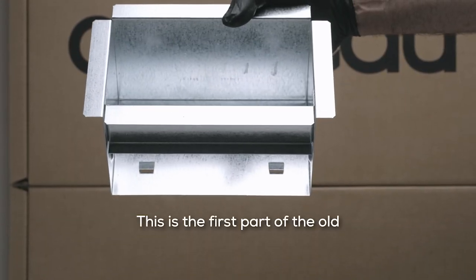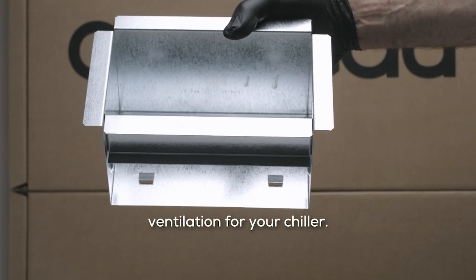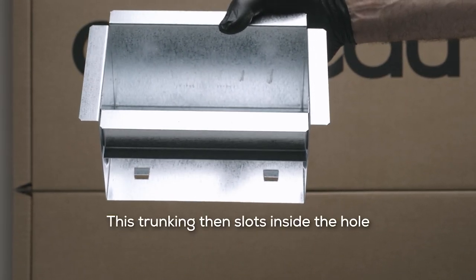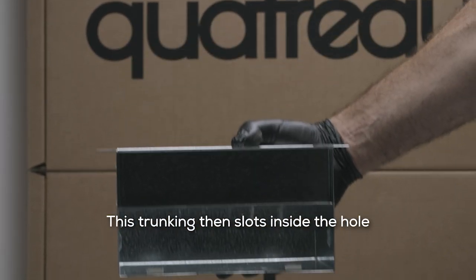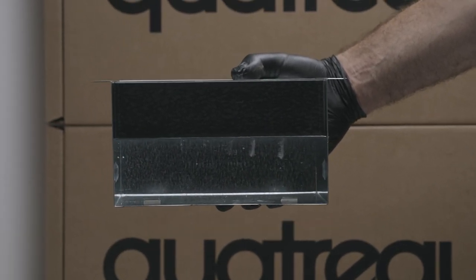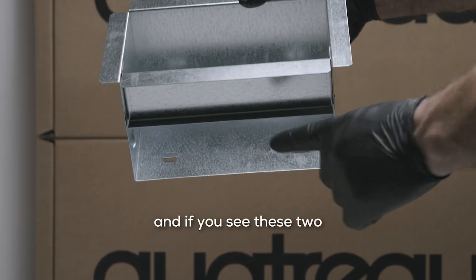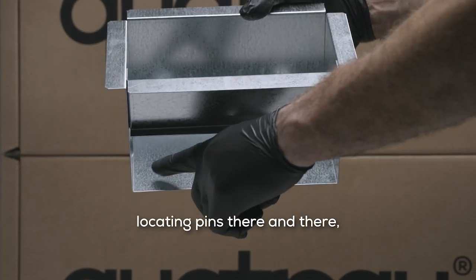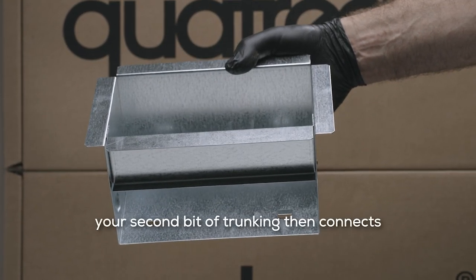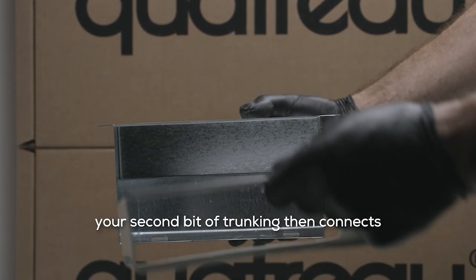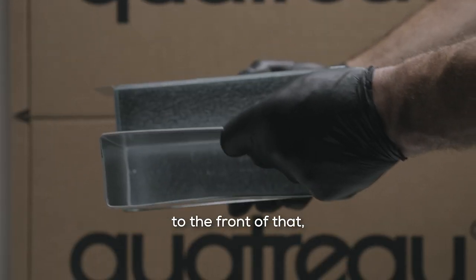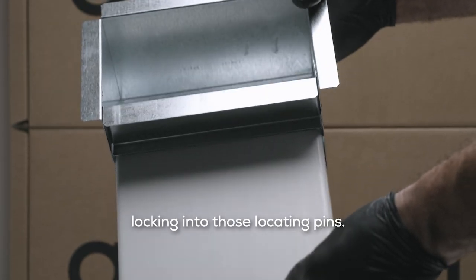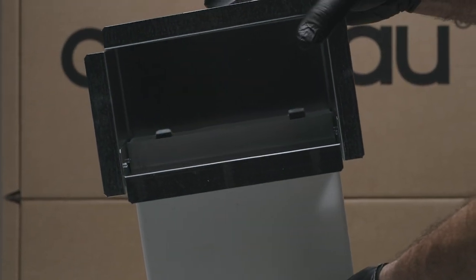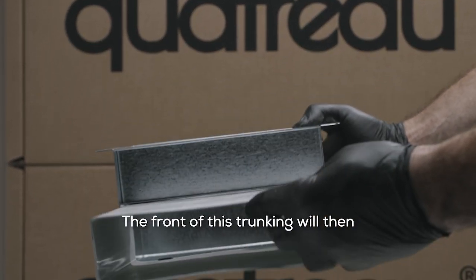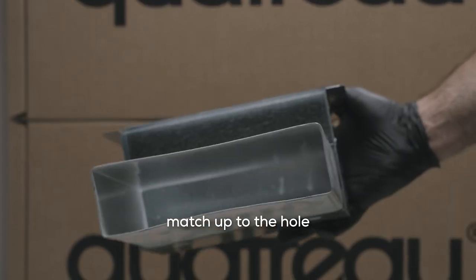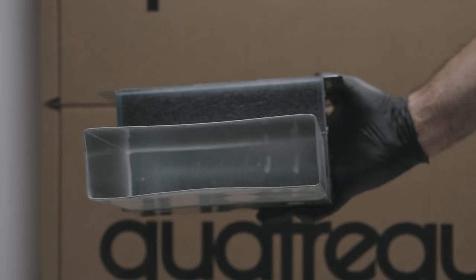This is the first part of your trunking for the ventilation for your chiller. This trunking then slots inside the hole in the kitchen cupboard. And if you see, there's two locating pins there and there. Your second bit of trunking then connects to the front of that, locking into those locating pins. The front of this trunking will then match up to the hole you've cut in the kick panel.